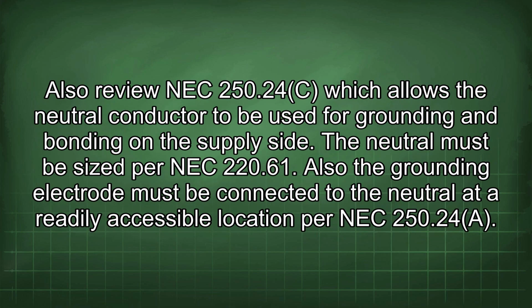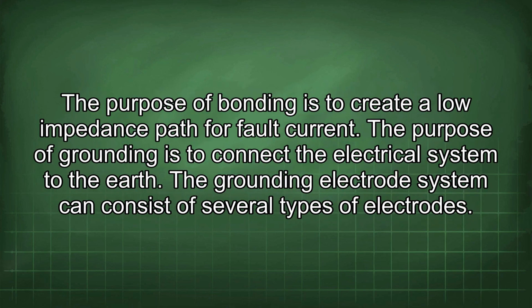Also review NEC 250.24(C), which allows the neutral conductor to be used for grounding and bonding on the supply side. The neutral must be sized per NEC 220.61. Also, the grounding electrode must be connected to the neutral at a readily accessible location per NEC 250.24(A). The purpose of bonding is to create a low impedance path for fault current. The purpose of grounding is to connect the electrical system to the earth.